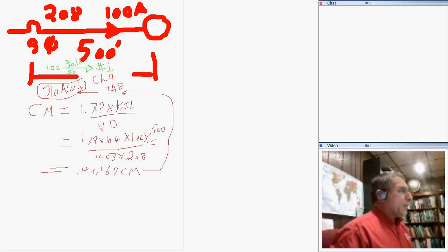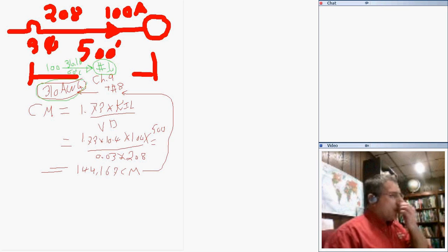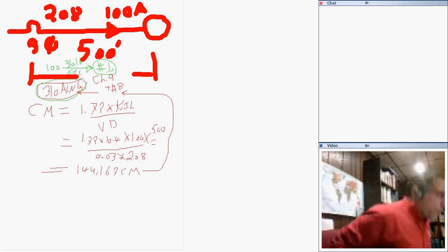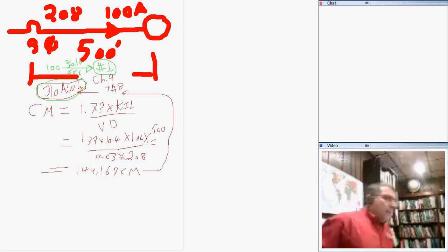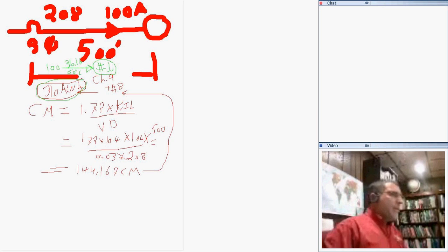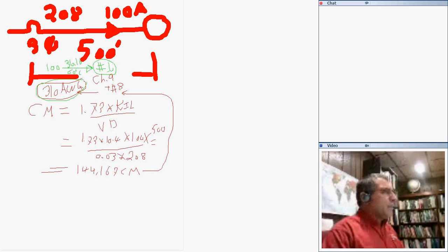The actual sizing, no derating, nothing, you came up, as we can see, with number 1, right? This is the 60 degree column, and this is, we came up with 3 aught. Which conductor do you think we're going to be using? We're going to be using 3 aught. Everybody agree with that, guys? 3 aught, the largest conductor based on these circumstances.